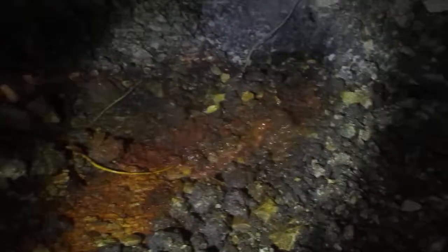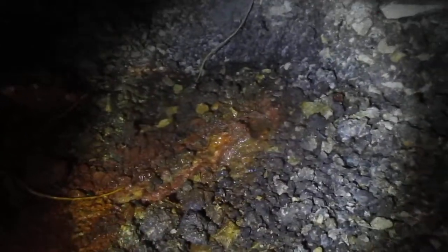Same thing over here — I don't know if you can see that very well — but you can see water dripping right there, and that's coming straight out of this metal duct work that's here in the crawl space. The air conditioning plenum there, you can just see how rusted and deteriorated that is at the bottom of the unit.